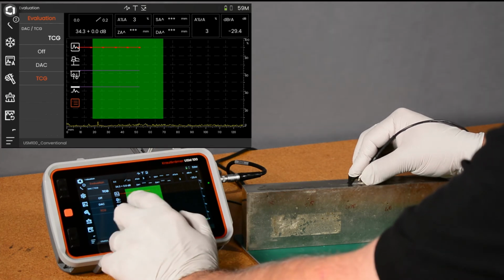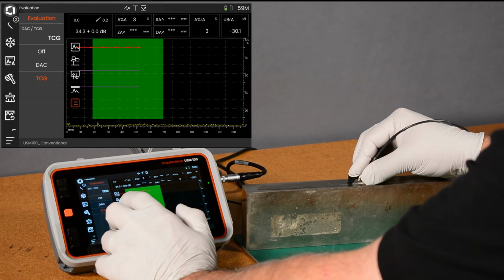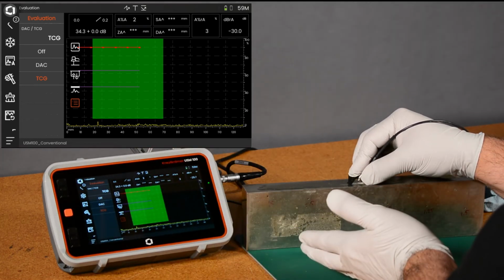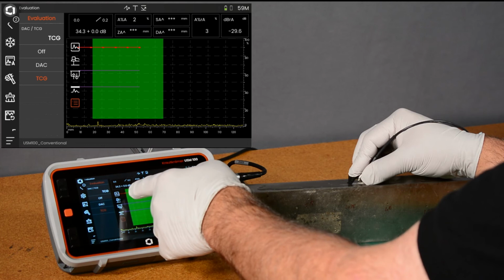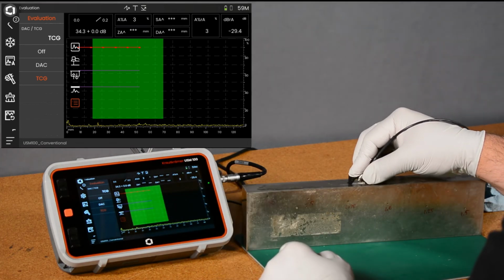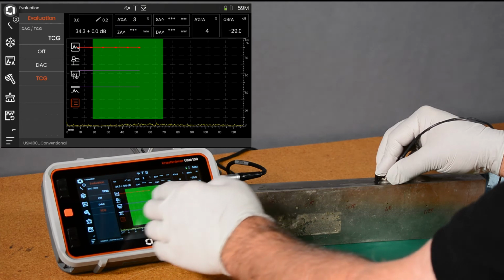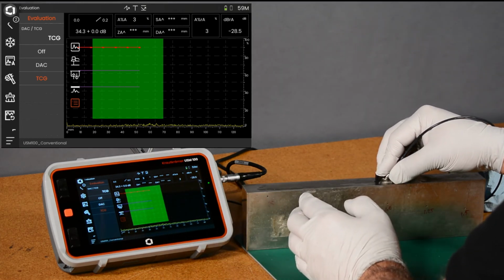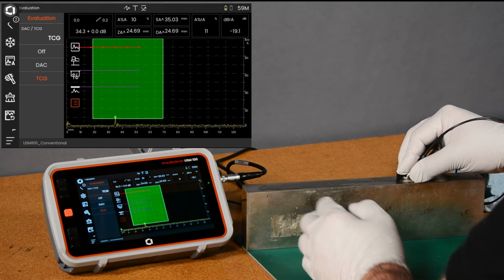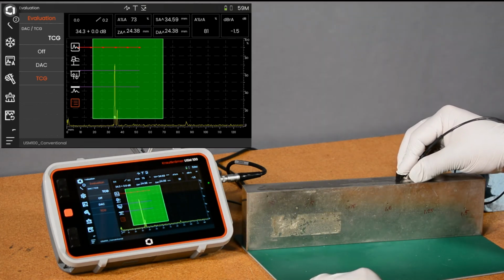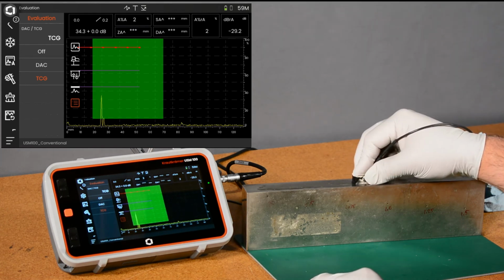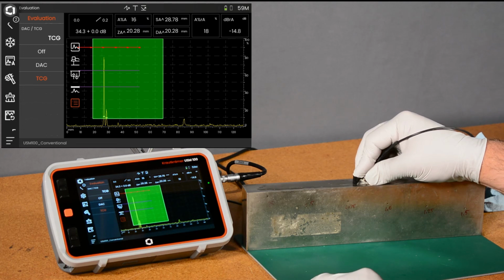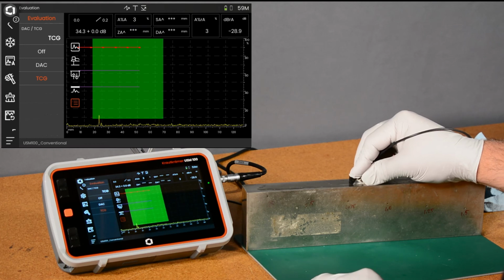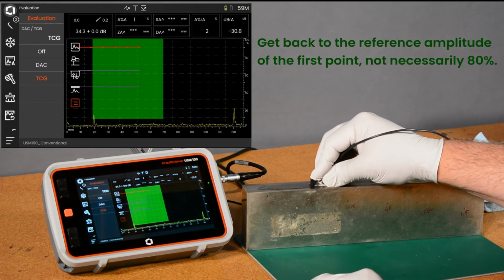And what this does is calculate the amount of gain required to match that amplitude curve. Now instead, we're going to make the curve flat at our reference amplitude, and we're going to vary gain as we go through time on the shot. So that has the effect of each one of these holes should now give us an equal amplitude, and it should come up to the reference line. So as I scrub across here and I see each one of my holes, if I'm doing my part with scrubbing the probe properly, I can get back to 80%.